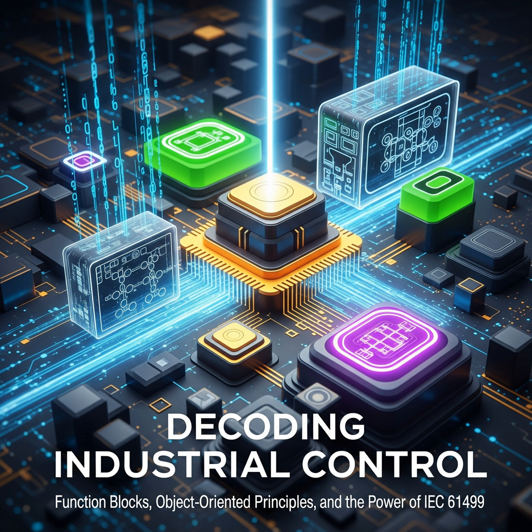Okay, so we have the blueprint, the type, and the unique creation, the instance. With that clear, it seems function blocks aren't all the same. The standard talks about different flavors, right? Basic, composite, service interface, and sub-applications. Exactly. Each one has a distinct role in building up the system. So what makes each one unique? Let's start with basic. Okay, the basic function block type. As the name suggests, it's the simplest. The standard says it's not decomposable into further function blocks. It's the bedrock. And how does it work? At its core, it uses something called an execution control chart, or ECC, that governs how its internal algorithms get executed based on events.